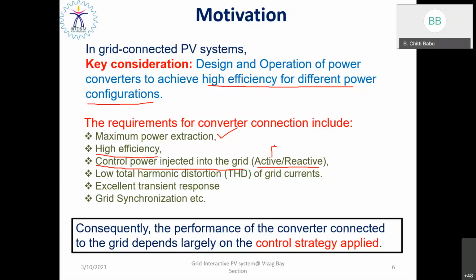The active power component is very essential to maintain the frequency stable, and the reactive power component is very essential to maintain the voltage profile constant. So in order to provide frequency stability as well as voltage stability, ultimately the power being injected into the utility grid must be controllable. That is another important requirement. And moreover, the power being injected into the utility grid has to be injected at a grid current which is sinusoidal. This implies the harmonic index we use in the electrical power system, called the total harmonic distortion. So the grid current should have a lower total harmonic distortion.